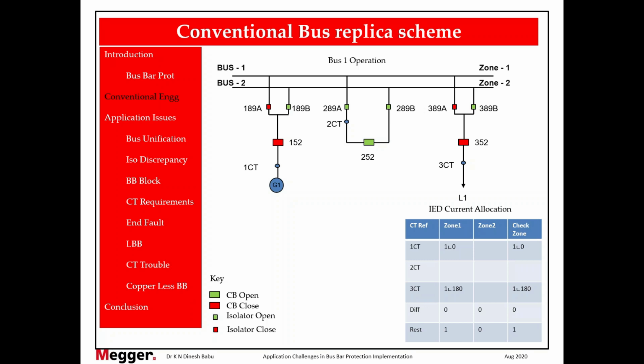Therefore, the check zone will not read any internal circulating current like bus section CT or bus coupler CT. Even if the CT is present, that current will not be read in the check zone. It's a fundamental principle which we use.